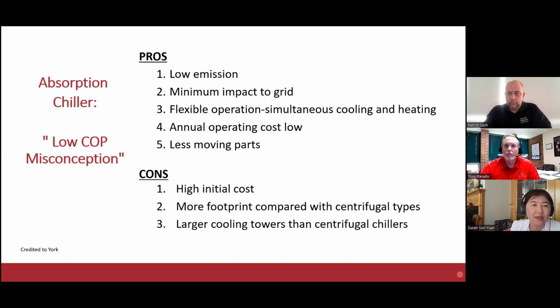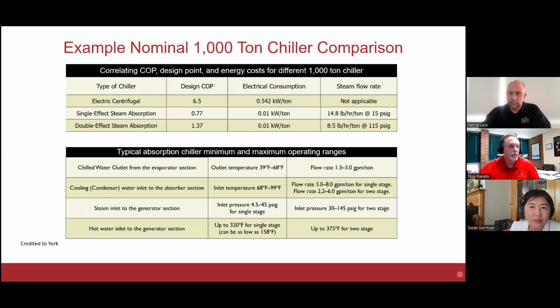The footprint is a little larger than centrifugal chillers, which also links to the initial cost. The cooling tower requires a little bit more capacity compared with a centrifugal chiller of the same cooling output. Next slide, please.